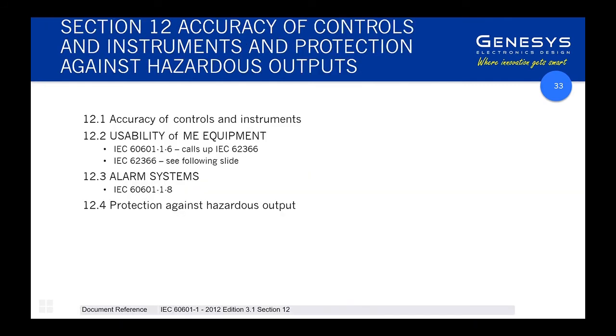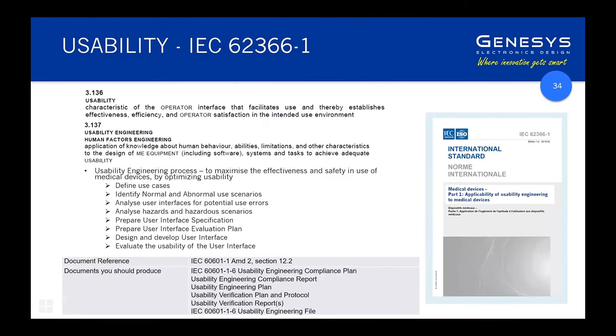Section 12 on accuracy of controls and instruments gets pretty specific. If you're displaying values, how accurate is the value being displayed? Does your measurement device measure it accurately enough? Does your software meet requirements to avoid corrupting values or applying an incorrect equation? You need sufficient safeguards in place to ensure any information displayed is sufficiently accurate, and your controls have accurate markings.